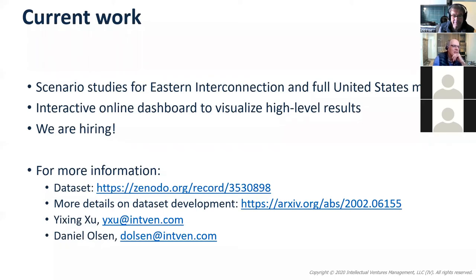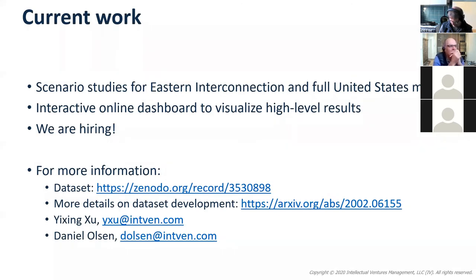A question about the validation: were there problems with a mismatch of generation and transmission? The biggest issue with infeasibility was the incompatibility of the demand profiles and the transmission capacity. We also had issues where the load flow looked kind of weird based on transmission constraints that were feasible but not really realistic. We iteratively ran the model, tuned it a little bit, looked at the congestion patterns, and tuned it more. Using a combination of transmission changes and cost curve changes, we settled on something with no unreasonable congestion anywhere, and total generation by zone and by generation type looks reasonable.